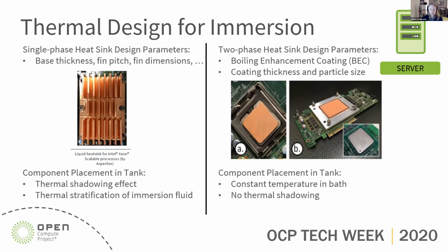For two-phase immersion, shown on the right side of this slide, it's about generating that simplified heatsink design using a boiling enhancement coating, or BEC, applied onto a metal surface. The parameters you can vary here are coating thickness and particle size, depending on the fluid you're using.